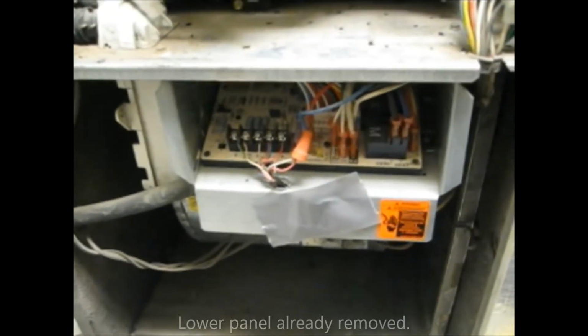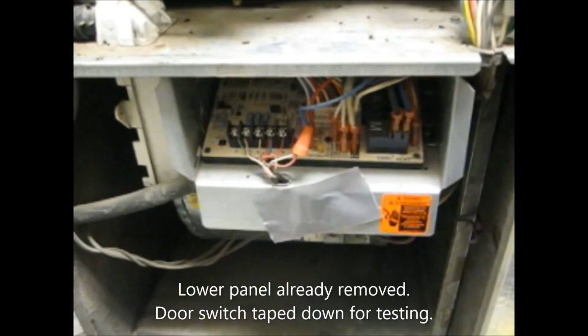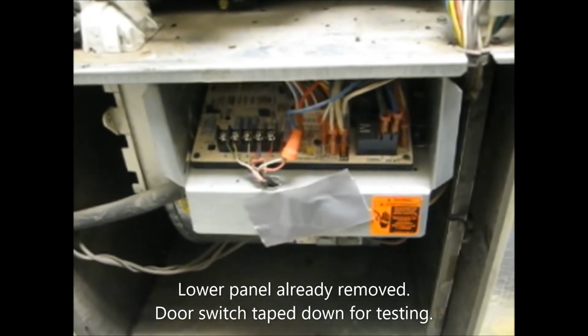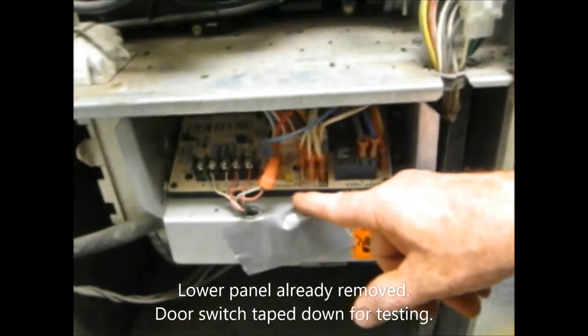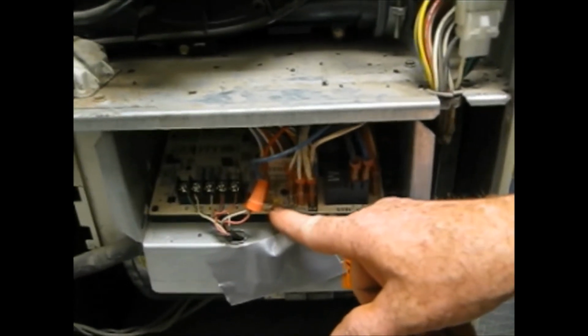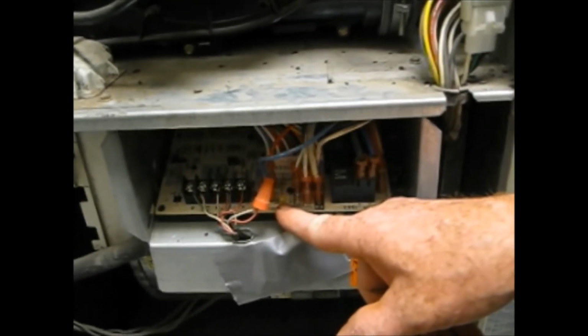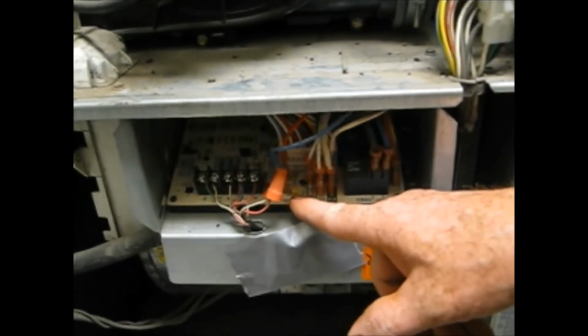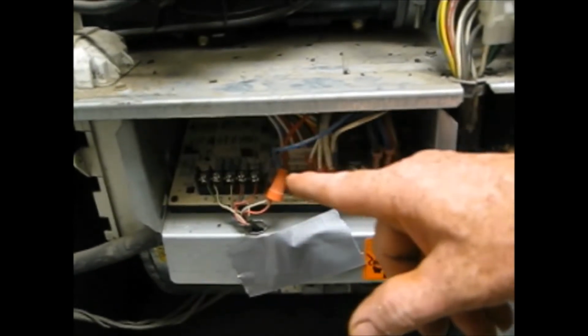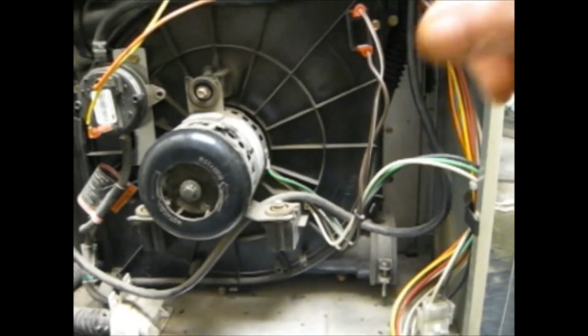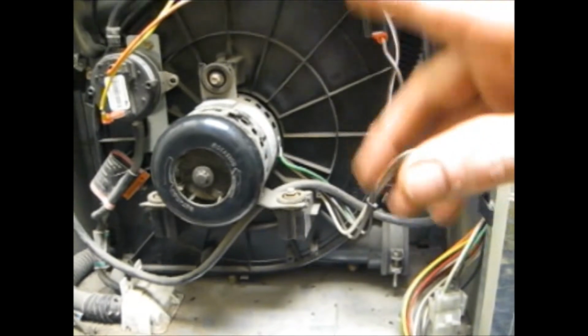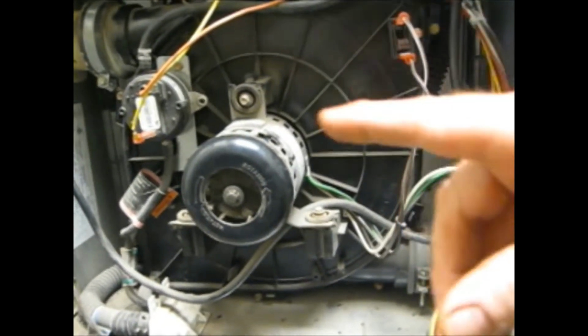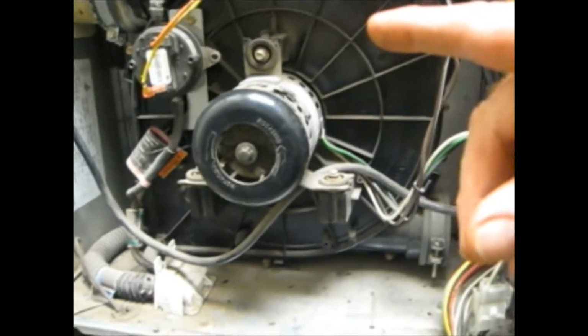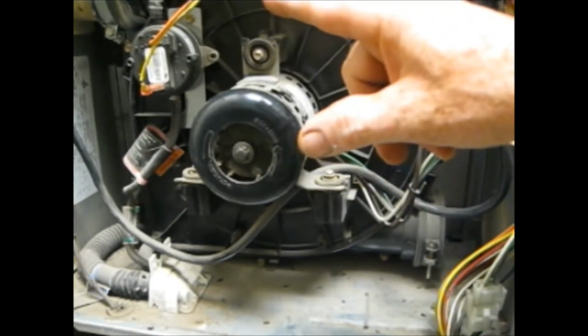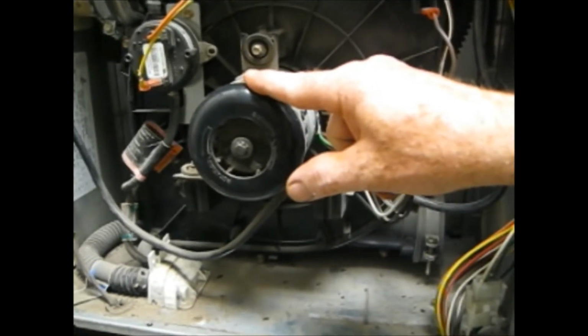When the signal comes in from the thermostat calling for heat, the first thing that happens, that signal goes to this control board. Now this could be called a computer, it can be called burner control, it's known by several names. The control board is going to look throughout the furnace to make sure all the safety switches are satisfied. If all the safety switches are satisfied, it's going to send power to this inducer motor.